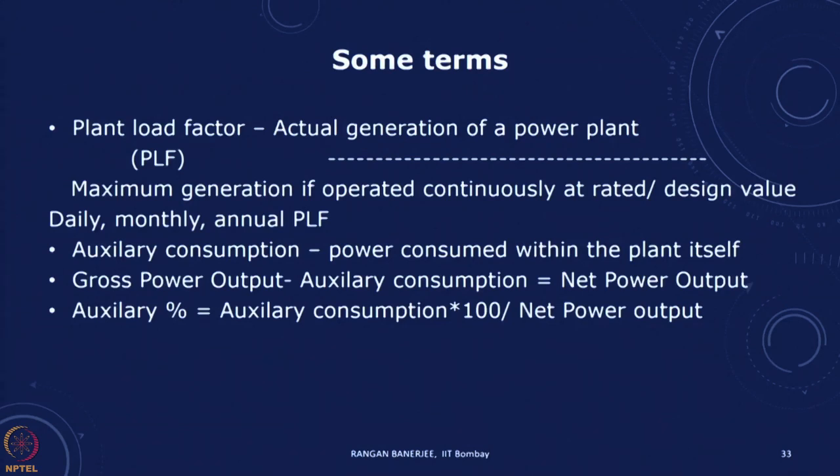Some of the terms we may want to look at when doing these overall balances: one is the plant load factor. Plant load factor of a plant is the actual generation over a period — a day, a month, or a year — divided by the maximum possible generation if operated continuously at the rated or design value. Typically these plants would like to operate at high plant load factor because whatever investment you have, you would like to recover it over a larger number of units, so electricity would be cheaper. But the plant load factor is dictated by the demand — you cannot supply electricity to the grid if there is no demand for it. That supply-demand matching is one of the key factors in the electricity system.